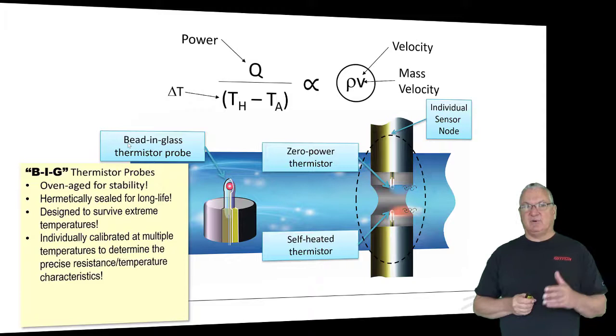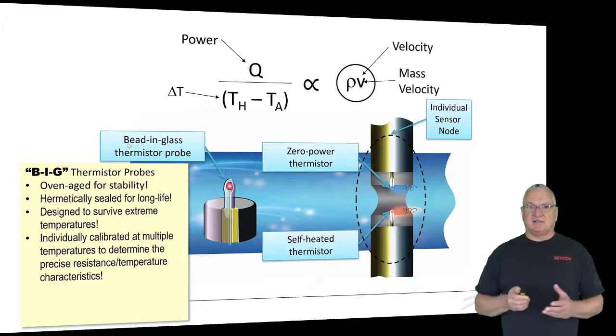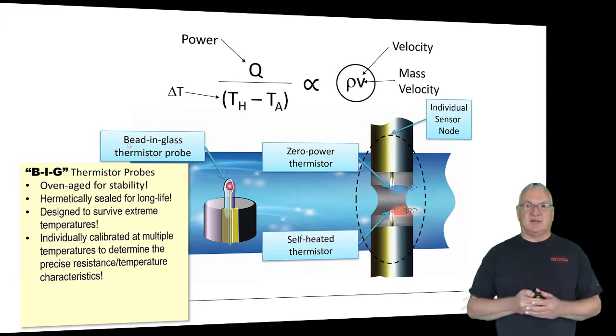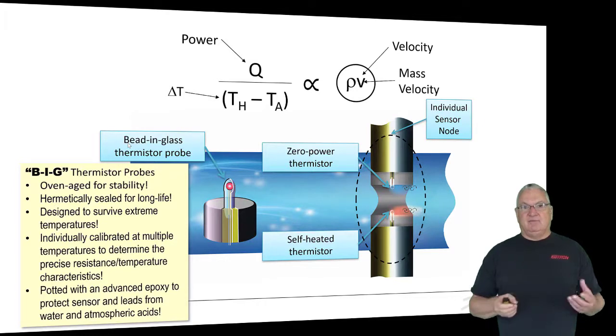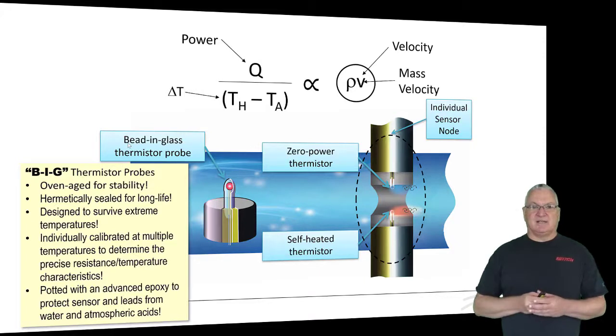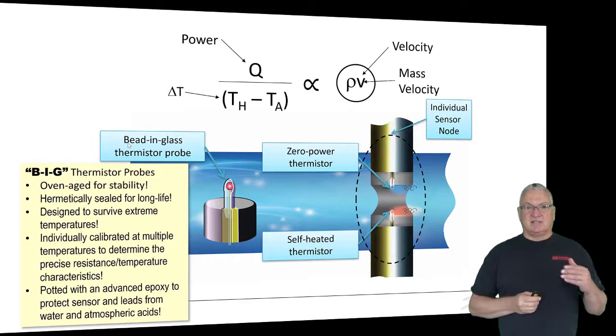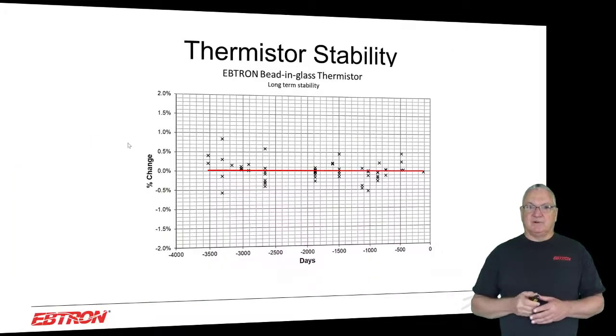So we actually have to put these in individual controlled temperature baths and get the resistance temperature characteristics. It's quite a process. We don't actually show it to anybody. It's fairly automated, but it's very unique. And then after we go through that calibration, we pot them with an advanced epoxy to protect the sensor leads from water and atmospheric acids. All right, so bead-in-glass thermistors is the thing that you want to remember.